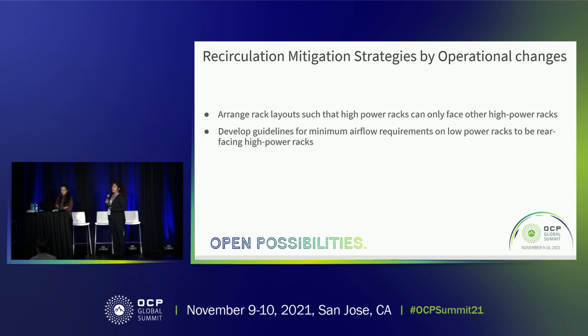So if we were not to make any design changes at our facility or rack design level, one way to mitigate recirculation would be to arrange the rack layout such that the high power rack is always rear facing another high power rack. And a second option would be to develop a framework such that we would define a minimum airflow requirement on the low power rack, meaning the fan control algorithm on the low power rack should be able to maintain a certain amount of CFM so that there is no scope for recirculation.